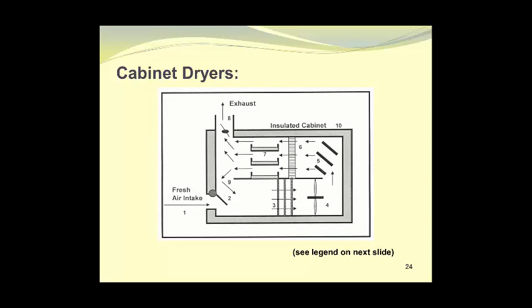At point number 6 we have air distribution plates which act to even out the flow of the air as it passes over the trays of wet material at location number 7. The air is now moist and can be exhausted. However, there may be enough heat and drying capacity left so that some of the air can be recirculated for energy efficiency. The arrangement then is to recirculate some of the air at point number 9 and to add makeup air through the fresh air intake, balanced with the exhaust valve at point number 8 where the exhaust is vented to the atmosphere.